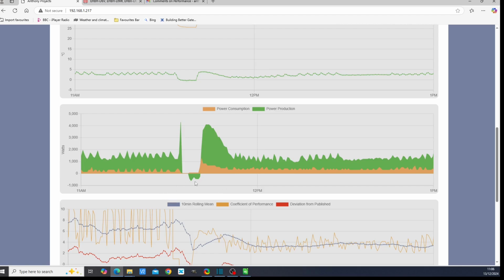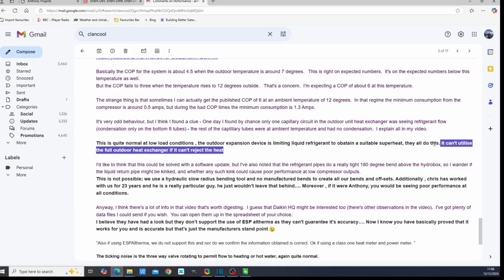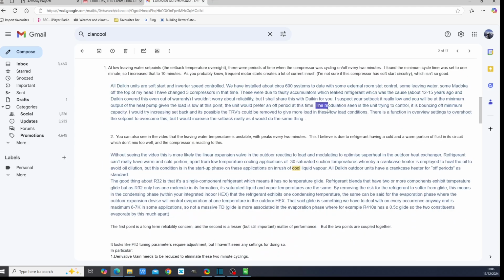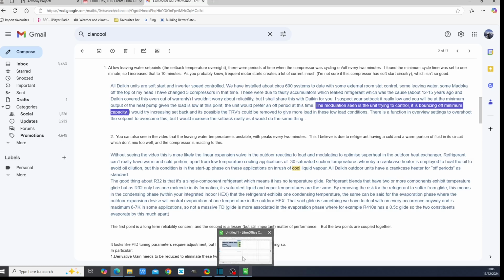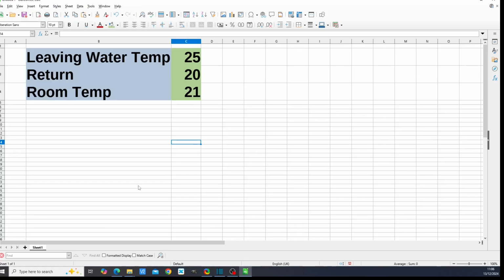Now, I raised this performance regime with my installer, and he's saying right here that the outdoor heat exchanger can't be fully utilized if the indoor heat exchanger can't reject the heat. He's saying that the modulation is bouncing off minimum capacity. So this is worth exploring in a little bit more detail. Now, one of the things I've got here is just a little bit of an illustration.